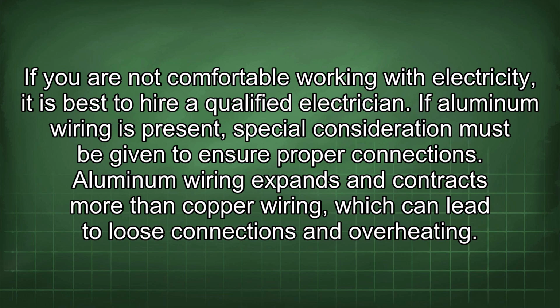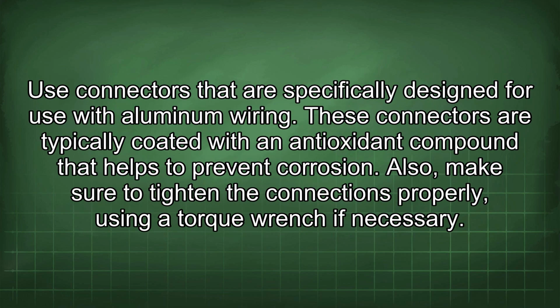If aluminum wiring is present, special consideration must be given to ensure proper connections. Aluminum wiring expands and contracts more than copper wiring, which can lead to loose connections and overheating. Use connectors that are specifically designed for use with aluminum wiring. These connectors are typically coated with an antioxidant compound that helps to prevent corrosion. Also, make sure to tighten the connections properly, using a torque wrench if necessary.